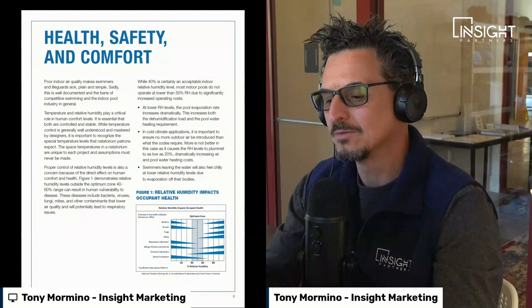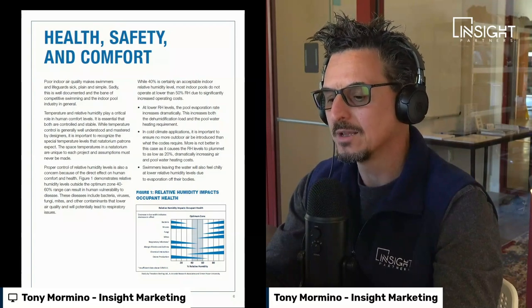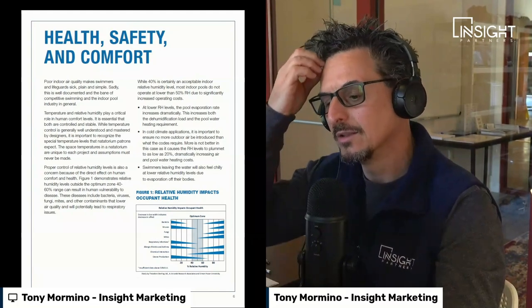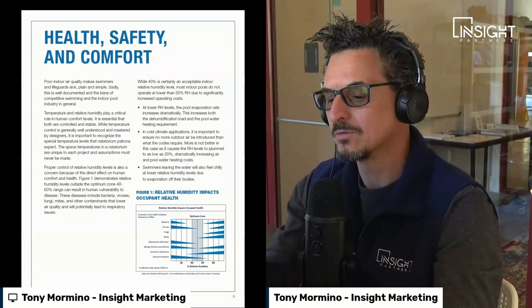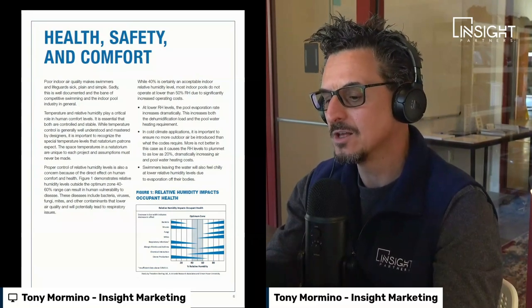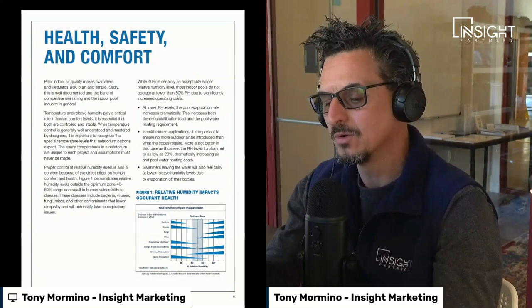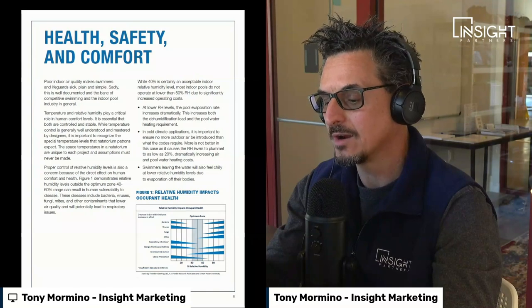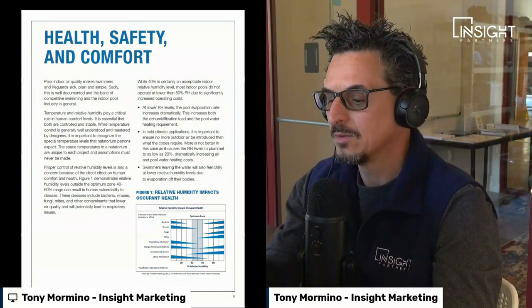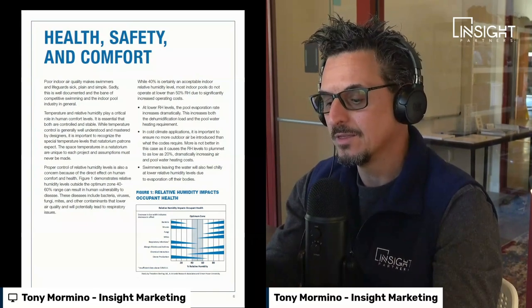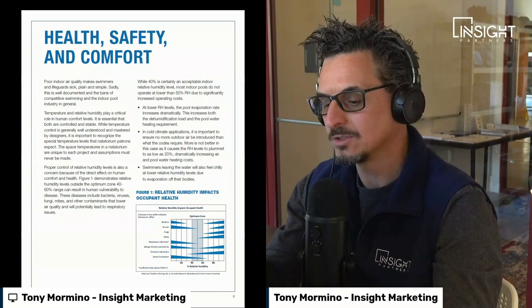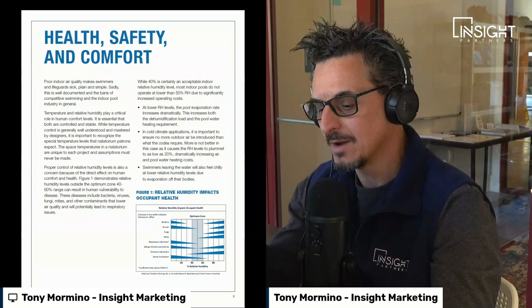While 40% is certainly an acceptable indoor relative humidity level, most indoor pools do not operate lower than 50% RH due to significantly increased operating costs. At lower RH levels, the pool evaporation rate increases dramatically, increasing both the dehumidification load and the pool water heating requirement. In cold climate applications, it is important to ensure that no more outdoor air be introduced than what the code requires — more is often not better, as it causes RH levels to plummet as low as 20%, dramatically increasing air and pool water heating costs.